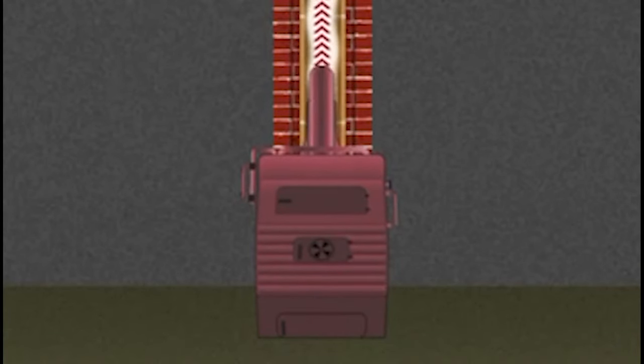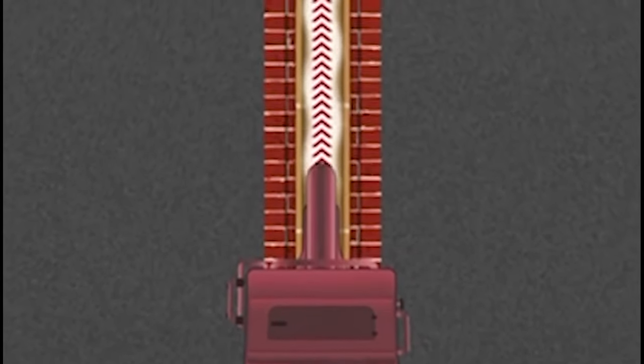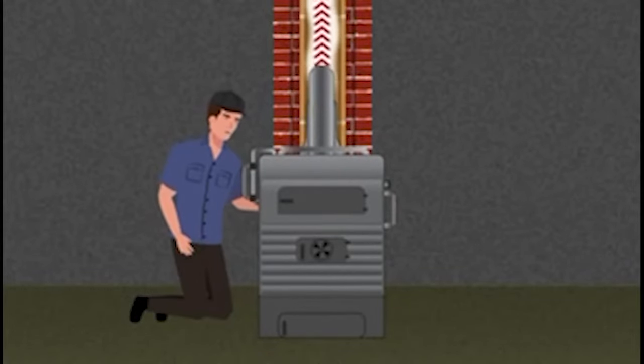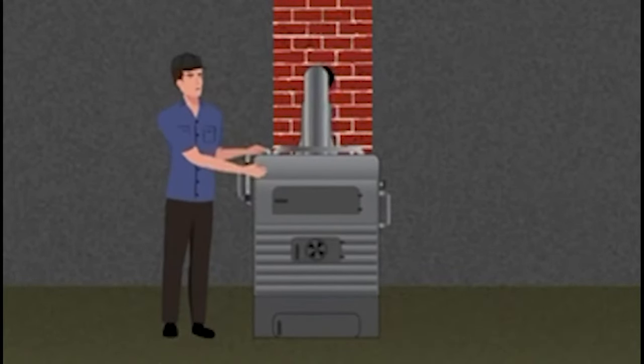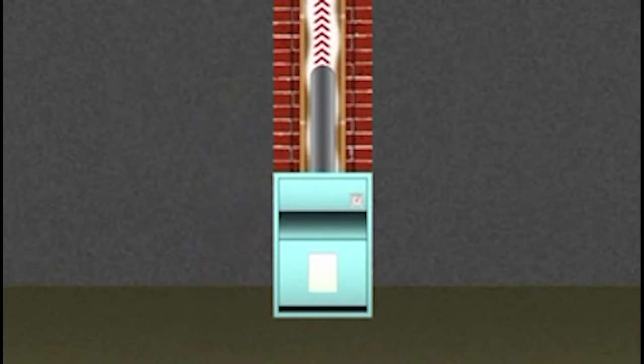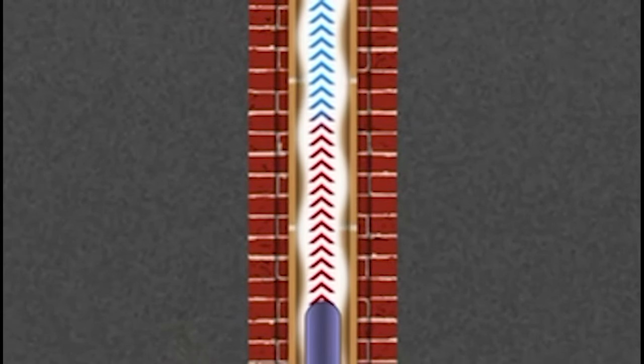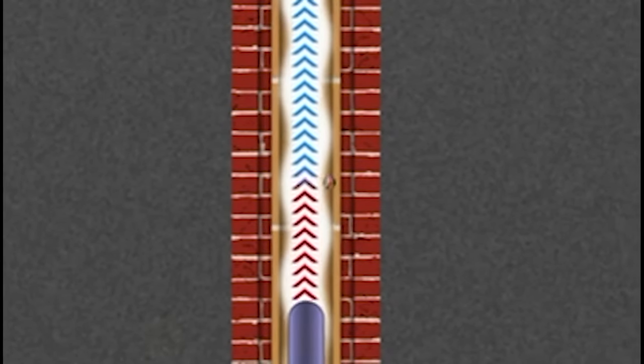The original chimney was sized for the original heating appliance, which operated at a higher temperature and drafted extremely hot. Over the years, tune-ups are performed, and newer, higher efficiency heating appliances are installed, causing units to no longer run at hotter temperatures. This makes it harder for the heat to rise out of the top of the chimney and create a safe, natural, consistent draft.